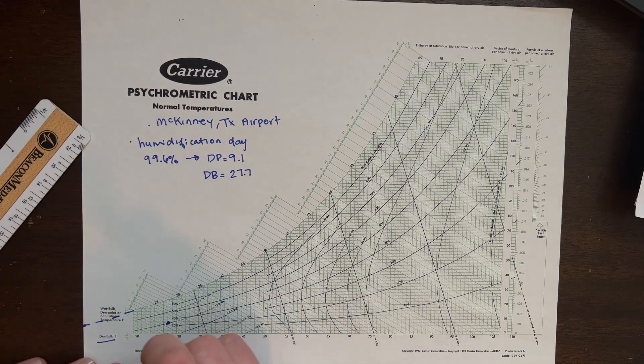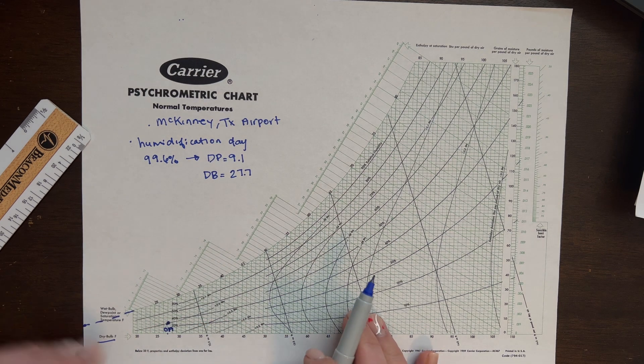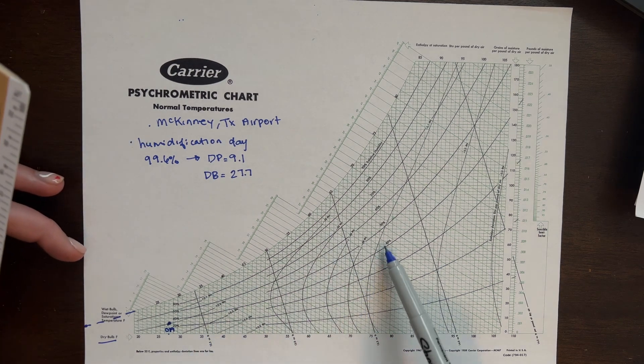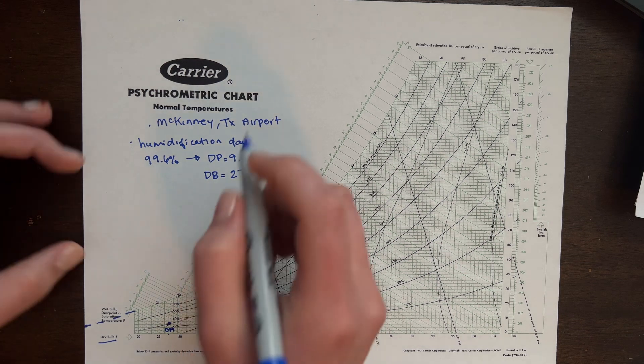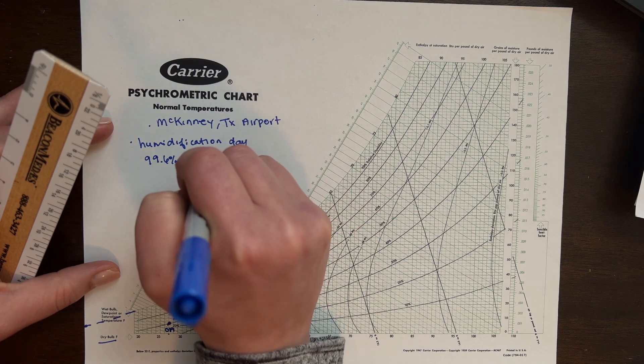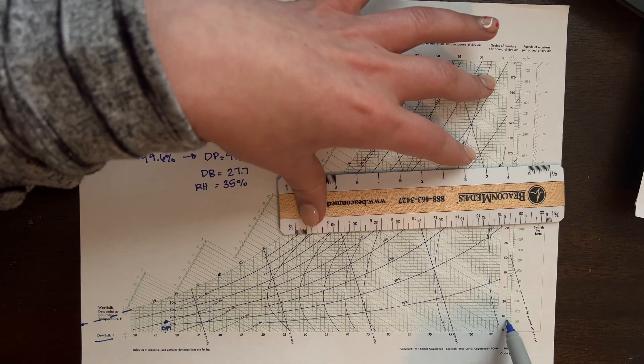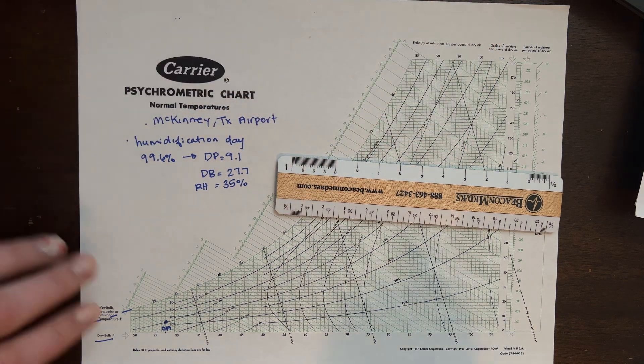And that is my outside air condition on my humidification day. Okay, that gives us about a relative humidity, about 35%. And then if we go all the way directly across to the right until we get to our grains, it's going to give us about eight grains of moisture.